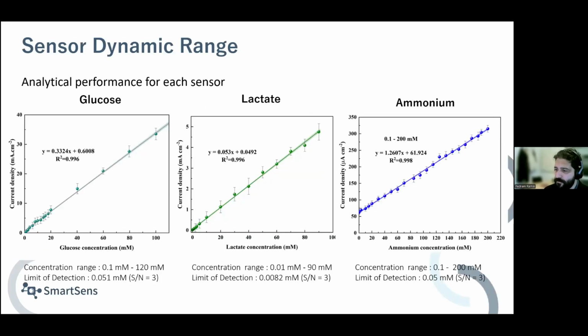Just to show you some of the results for our 3 measurements of glucose, lactate, and ammonium, they show the dynamic range. It's very linear. So you see the current density versus the concentration of the analytes. For glucose, we can measure from 0.1 to 120 millimolar, a very straight line. Similar for lactate, 0.01 millimolar, very low concentration, all the way to 90. And for ammonium, it's actually up to 200 millimolar. So very broad dynamic range, and this is actually exceptional. And the linearity is also very high.